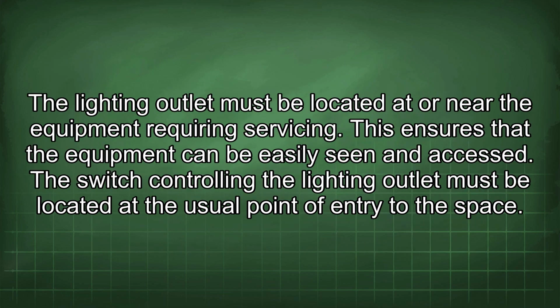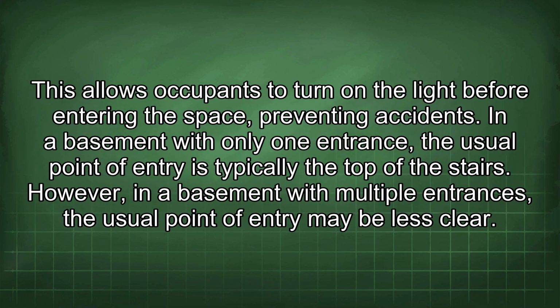The lighting outlet must be located at or near the equipment requiring servicing. This ensures that the equipment can be easily seen and accessed. The switch controlling the lighting outlet must be located at the usual point of entry to the space. This allows occupants to turn on the light before entering the space, preventing accidents. In a basement with only one entrance, the usual point of entry is typically the top of the stairs.